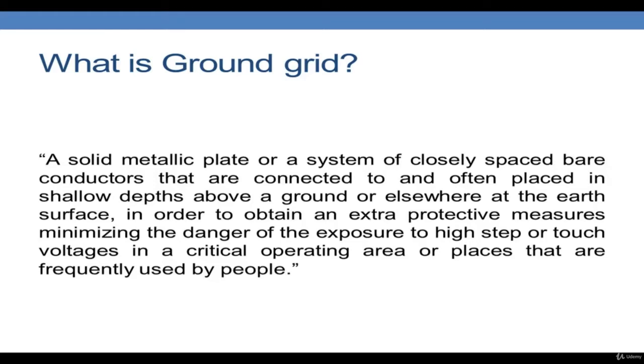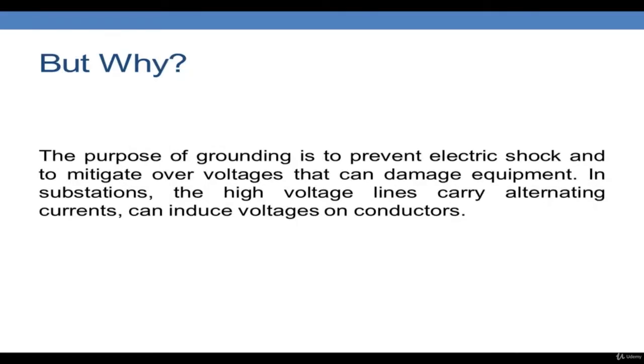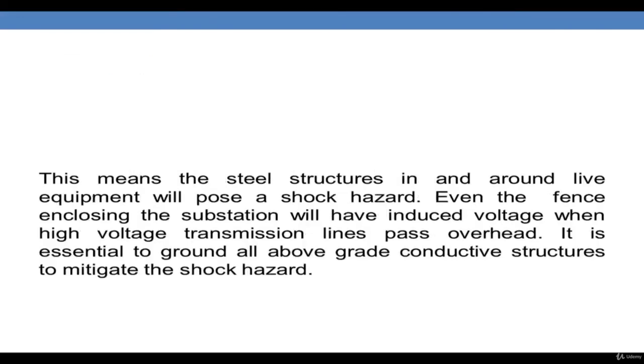So basically a ground grid is a system of bare conductors that are buried below the earth's surface or above the earth's surface, which is used for protective purposes. So why do we need earth grids or the earth mat? The purpose is to prevent electric shock and to mitigate overvoltages that can damage equipment. In substations, high voltage lines carry alternating currents which can induce voltages on conductors. This means that the steel structures in and around live equipment will pose a shock hazard. Even the fence enclosing the substation will have induced voltages when a high voltage transmission line passes overhead. So it is essential to ground all the above conductive structures to mitigate the shock hazard.